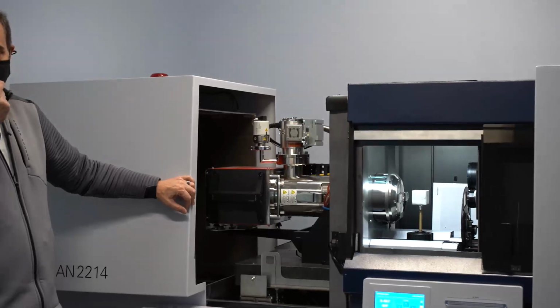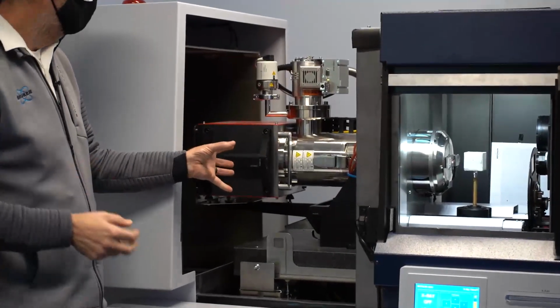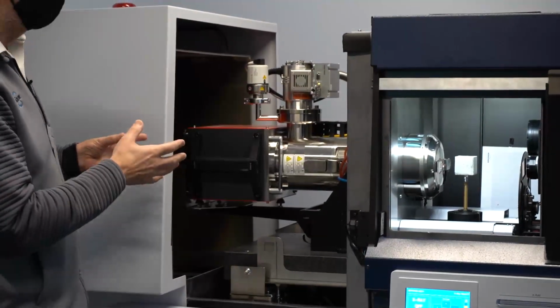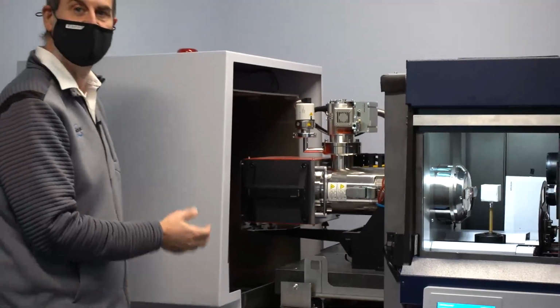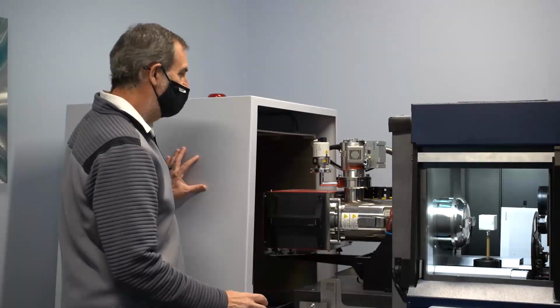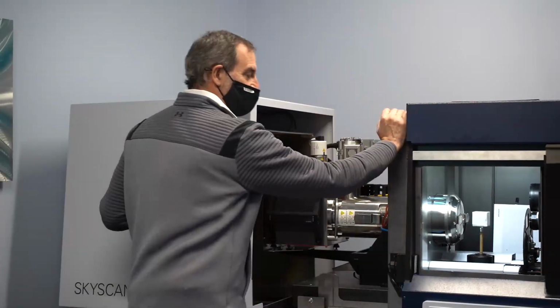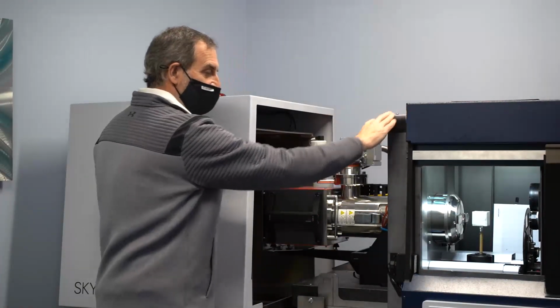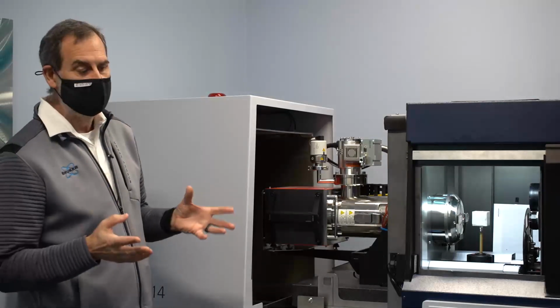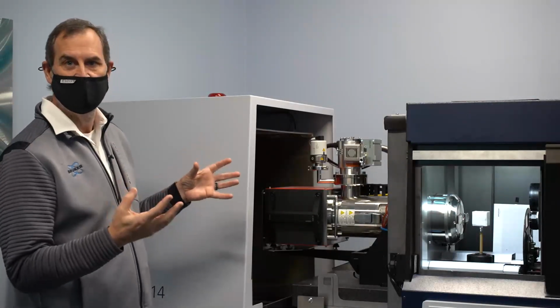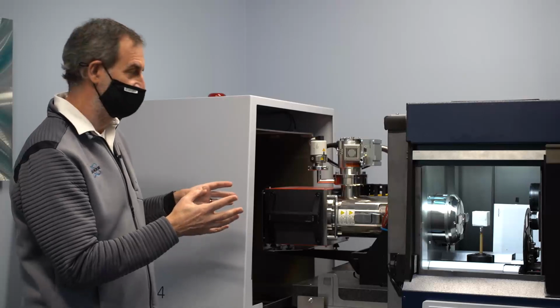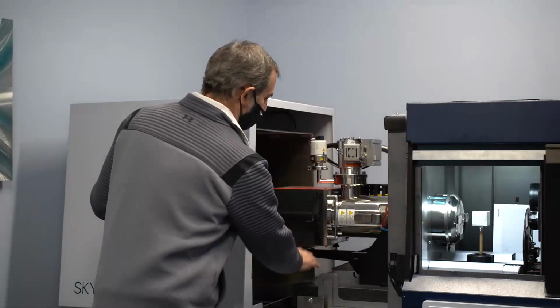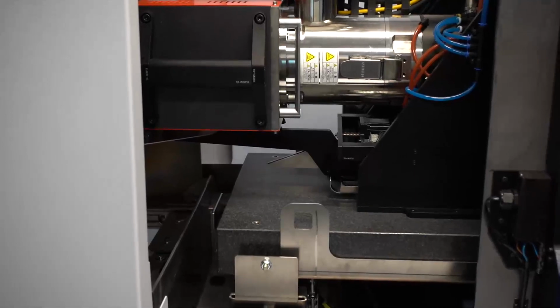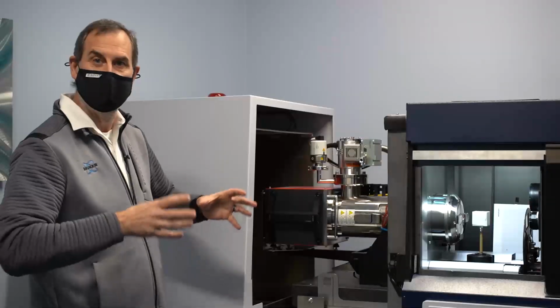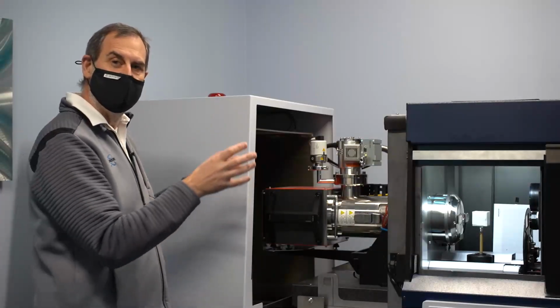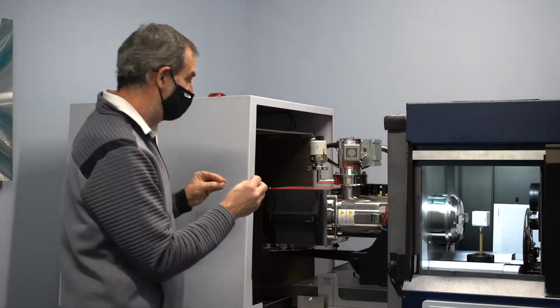Now, the engine behind the system is this X-ray source. This is a very high-tech X-ray source, very powerful. It's capable of 160 kilovolts, but even with that high-powered X-ray source, the system has a large lead enclosure that meets all the high safety standards. That means that you don't have to do any special infrastructure to put the system into place. It also rests on this large granite table, and the granite air table is there to isolate the lab vibrations from the instrument. That allows you the ultimate resolution.